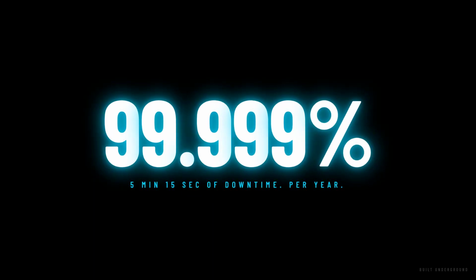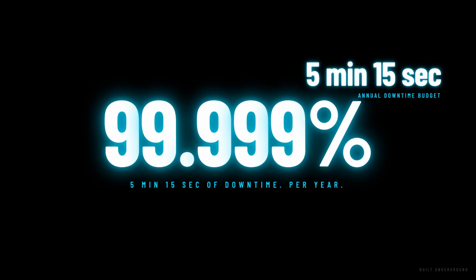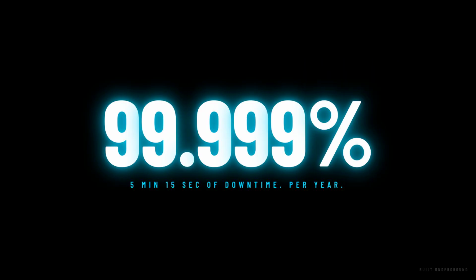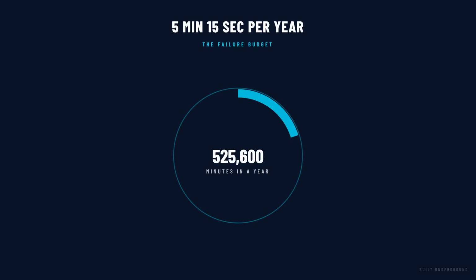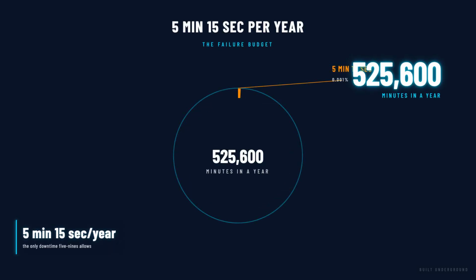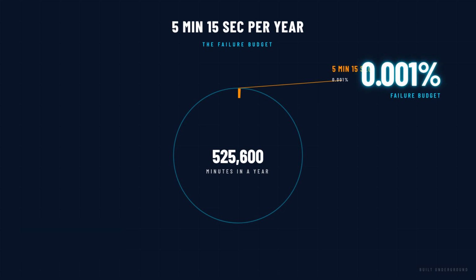That number is the standard the data center industry is built around. It is called five nines availability. It means a facility can be offline for a total of 5 minutes and 15 seconds in an entire year and still meet its contractual obligation. 5 minutes in a year of 525,600 minutes. That is a failure budget of 0.001%.